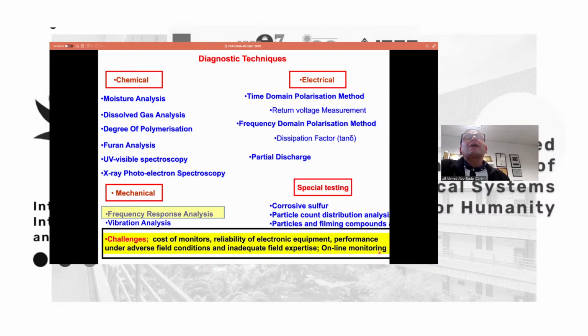Also, the main challenge here is that some of these techniques must be conducted offline. You have to take your transformer out of service, which will cause interruption to the power supply. So can we come up with online techniques? That's the main challenge in either research or industry practice.